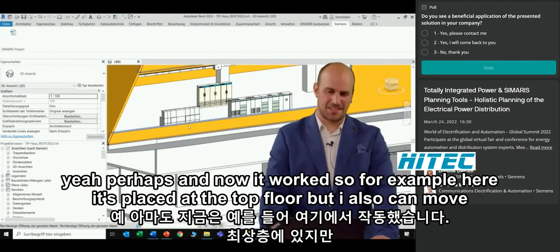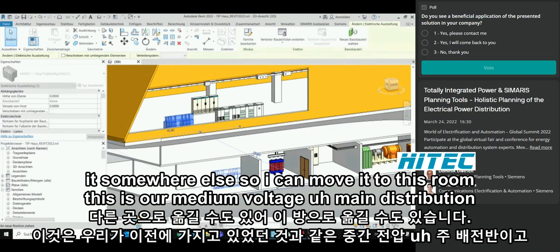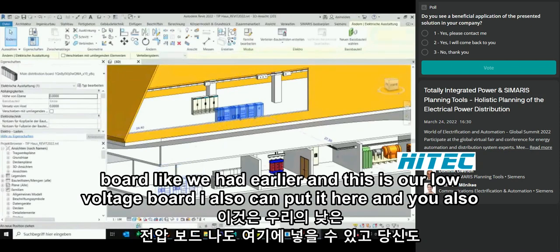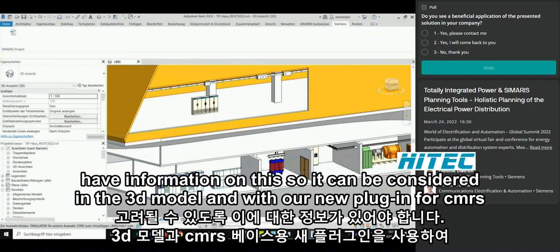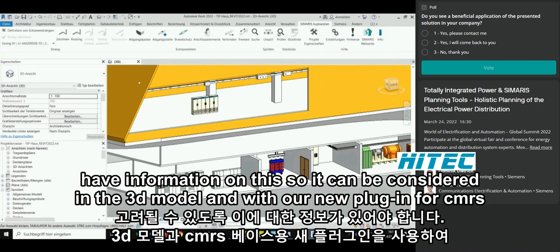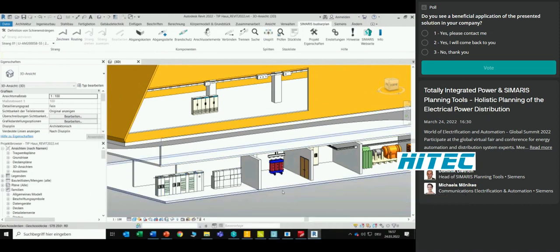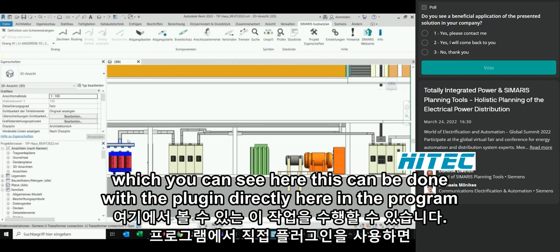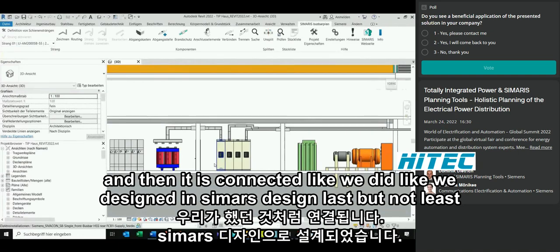With our plugin for Revit, you can import all information created in Simaris Project directly into the 3D program, with all information connected to the switchboard as a configured, orderable model. For example, the medium-voltage main distribution board and low-voltage board can be placed and moved to the correct rooms. With our new plugin for Simaris Busbar Plan, you can also draw the busbar trunking system connecting, for example, the transformer with the low-voltage switchboard — done directly in the program with all connections as designed in Simaris Design.